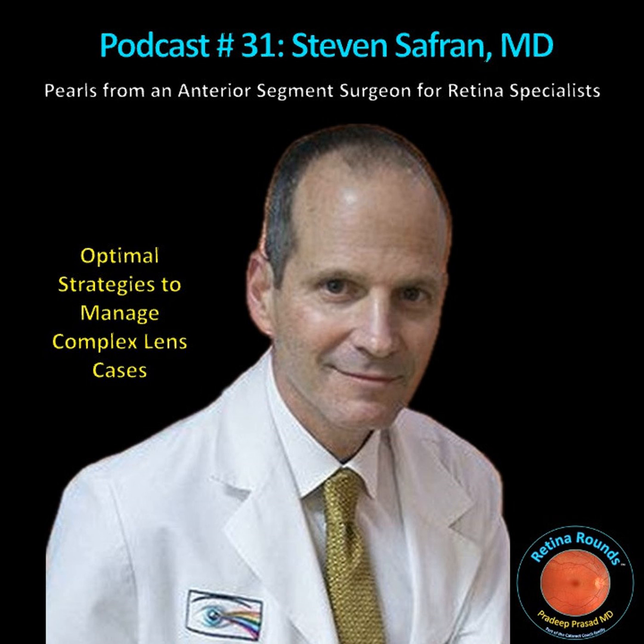They're the only lenses in the United States that have in their directions for use that they are approved for sulcus placement: the CZ70BD, which requires a 7 millimeter incision, and the LI61AO, the three-piece silicone. And those are the best lenses if you want to put a lens in the sulcus.